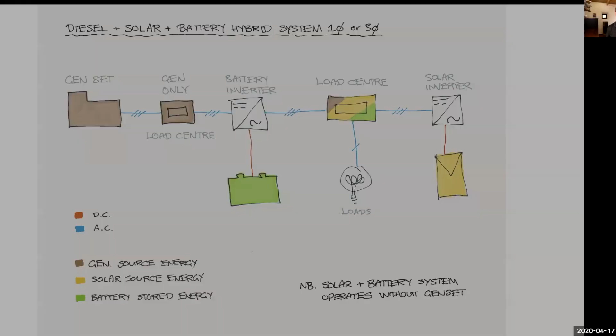Actually, I might have a go at trying to draw this - it might be a little messy since I'm using a mouse. What Craig's referring to is sometimes called black start protection. One of the problems with an AC coupled system, as I've drawn it here, is that if this battery system turns off because you've run out of power overnight and completely flattened the battery, that inverter will turn off. If that inverter turns off, the solar inverters have nothing to synchronize with. So even though the sun comes up in the morning, nothing's going to happen - you've got sun on the solar panels connected to a solar inverter, but no power, and no way of charging that battery. That's called a black start condition.